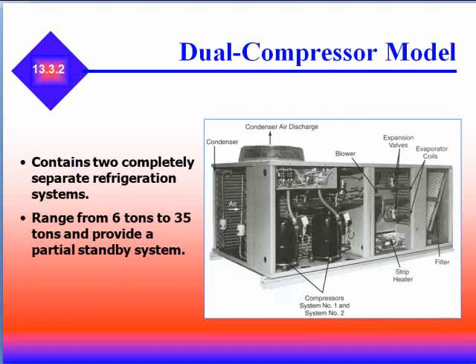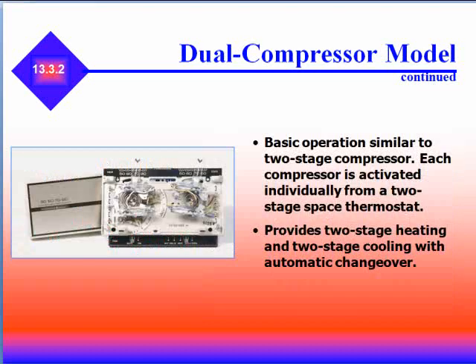Dual compressor models contain two completely separate refrigerant systems. They range from 6 tons to 35 tons and provide a partial standby system. Dual compressor models have basic operations similar to a two-stage compressor, and each compressor is activated individually from a two-stage thermostat. They provide two-stage heating and cooling with automatic changeover.